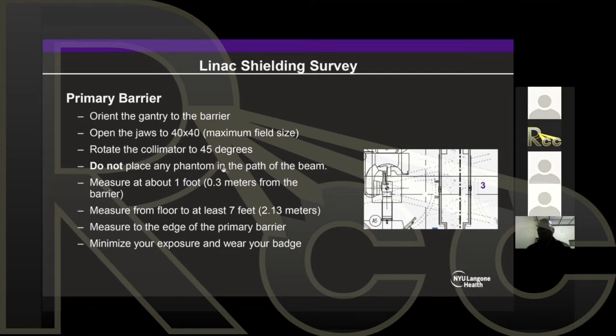And of course for the primary barrier, you're not gonna place any phantom in the path of the beam. And again, this is also worst case scenario, right? When you're treating, you're gonna have a patient there, there's gonna be attenuation. But for our survey measurements, we're just gonna leave it empty. So it's exactly like the worst situation.